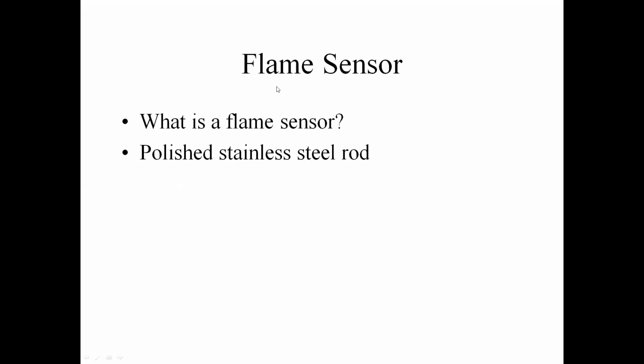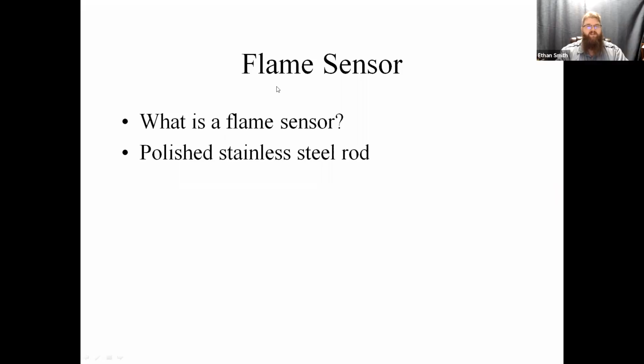Our furnaces are installed in a laundry room. I've seen that laundry fabric softeners, that type of thing gets in the air. Yep, chemicals will corrode flame sensors and it makes them rust. You can rust a stainless steel rod. It's not that it doesn't rust, it just doesn't rust as readily. So chemical environments will cause buildup or rust on flame sensors, and that stuff's all not electrically conductive.